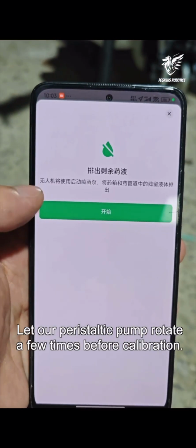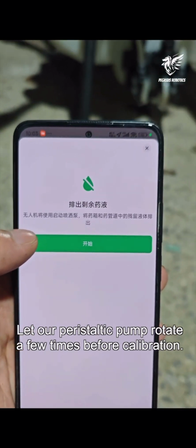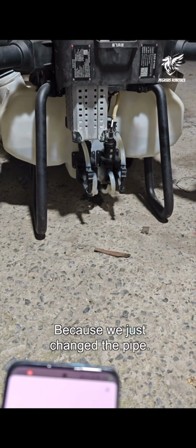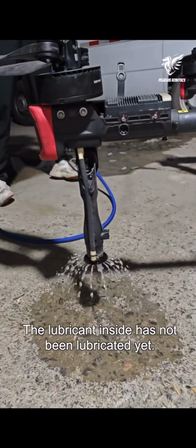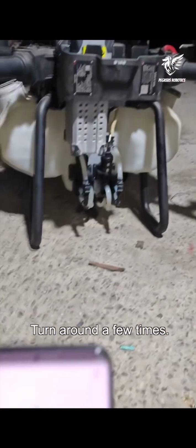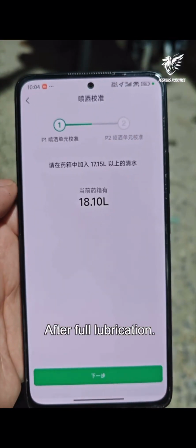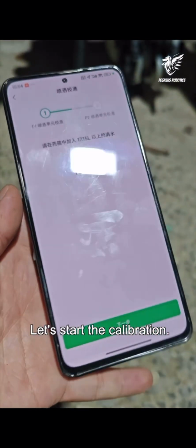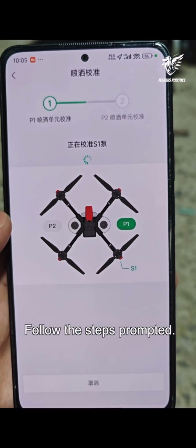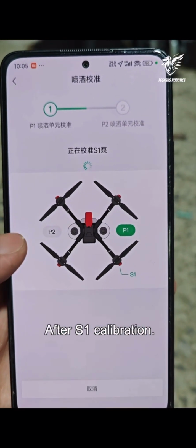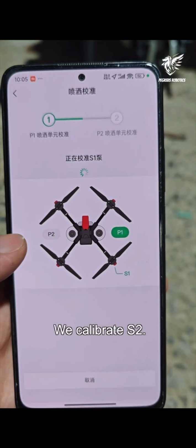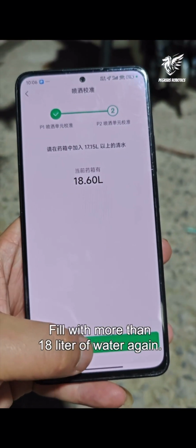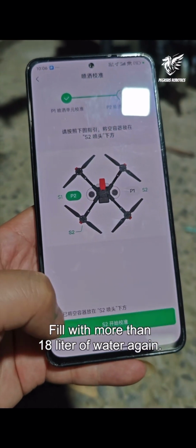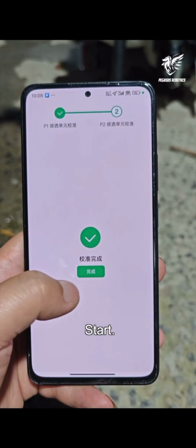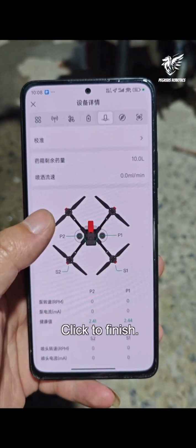Let our peristaltic pump rotate a few times before calibration. Because we just changed the pipe, the lubricant inside has not been lubricated yet. Turn around a few times. After full lubrication, let's start the calibration. Follow the steps prompted. After S1 calibration, we calibrate S2. Fill with more than 18 liters of water again. Start. After calibration, click to finish.